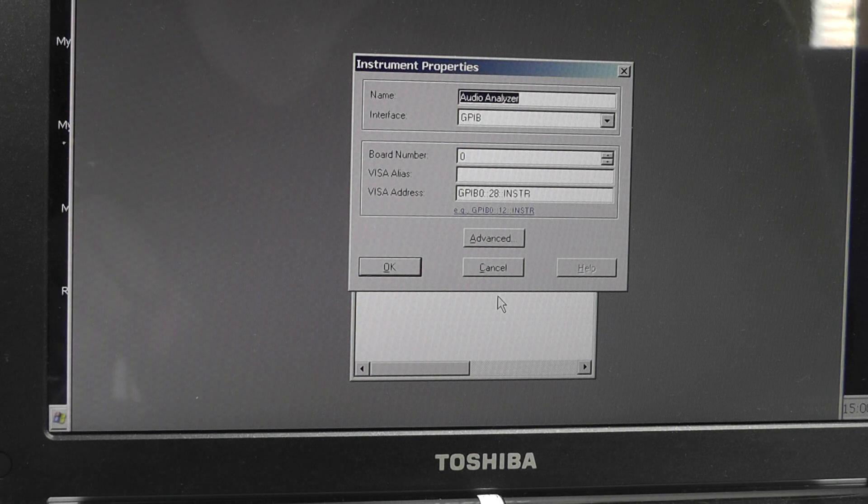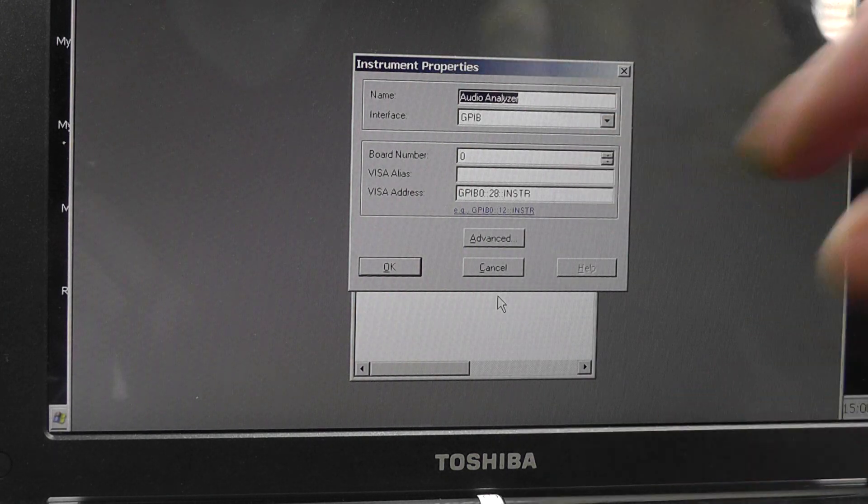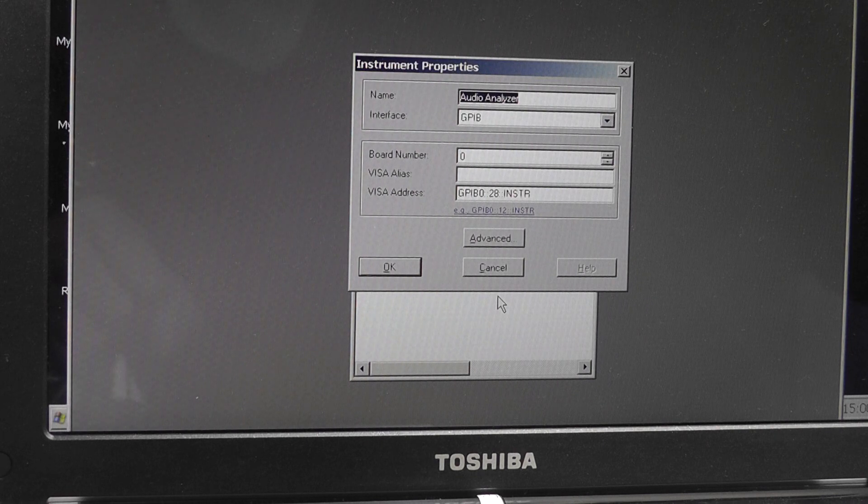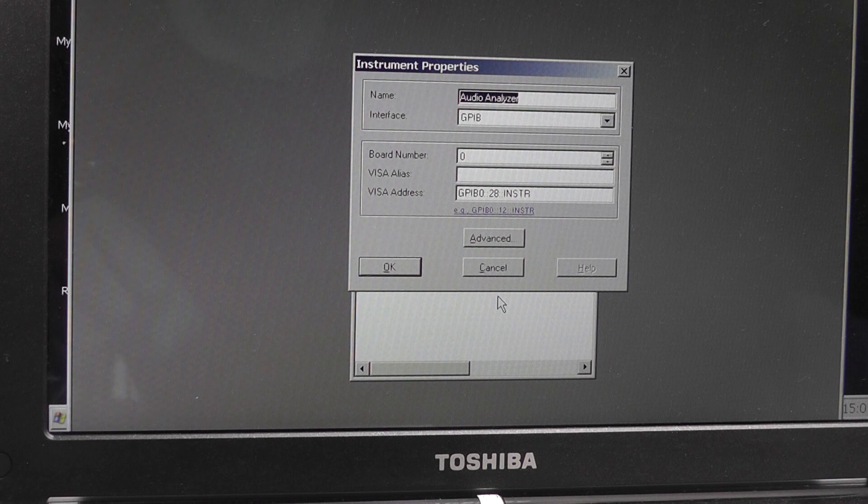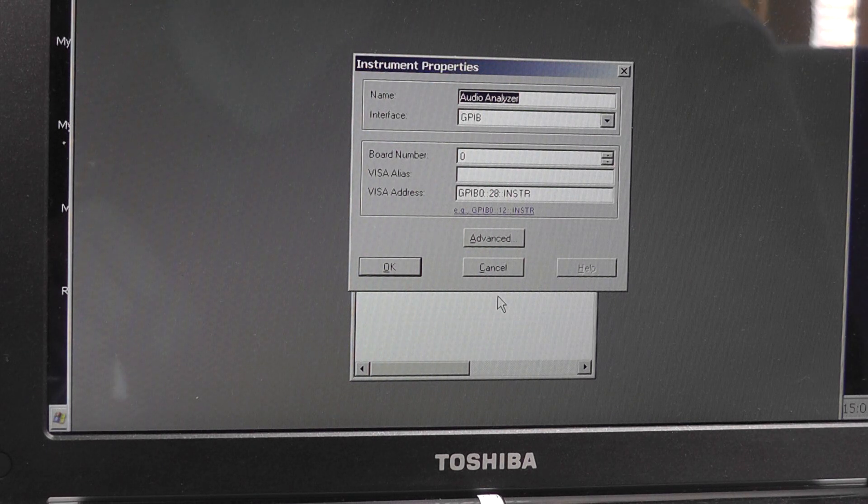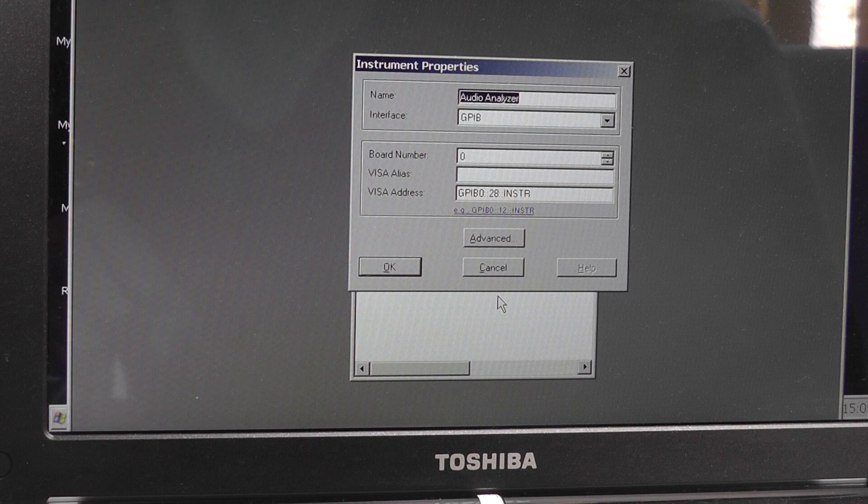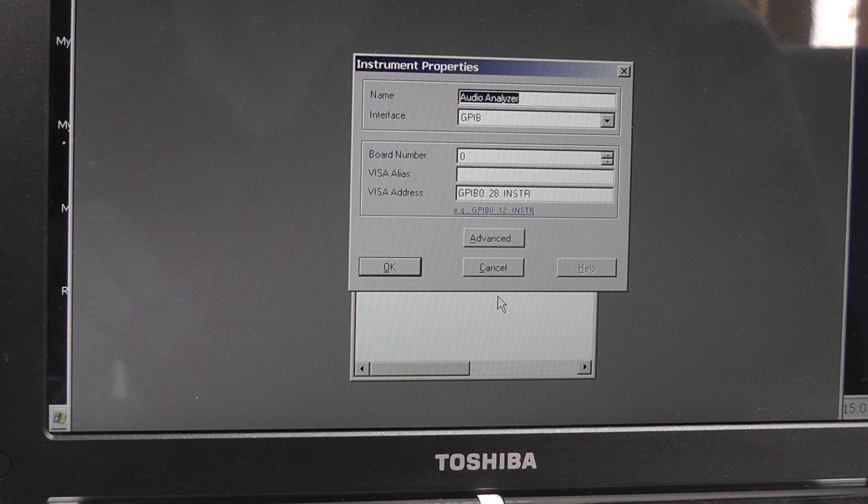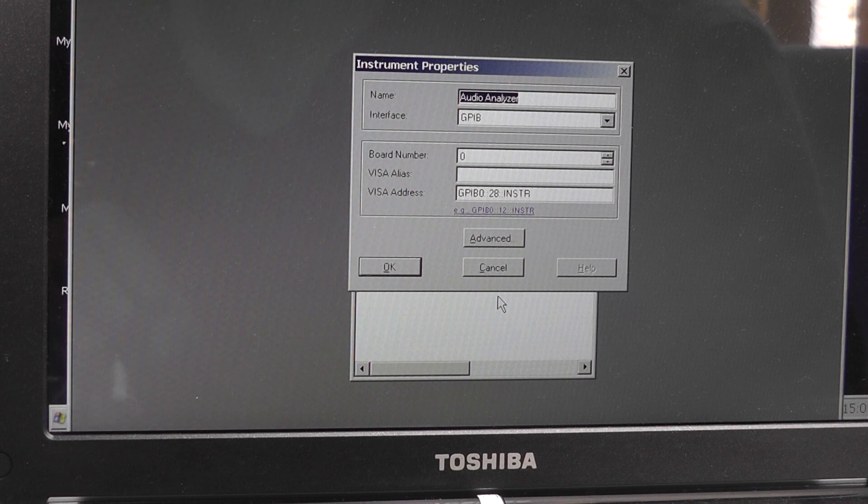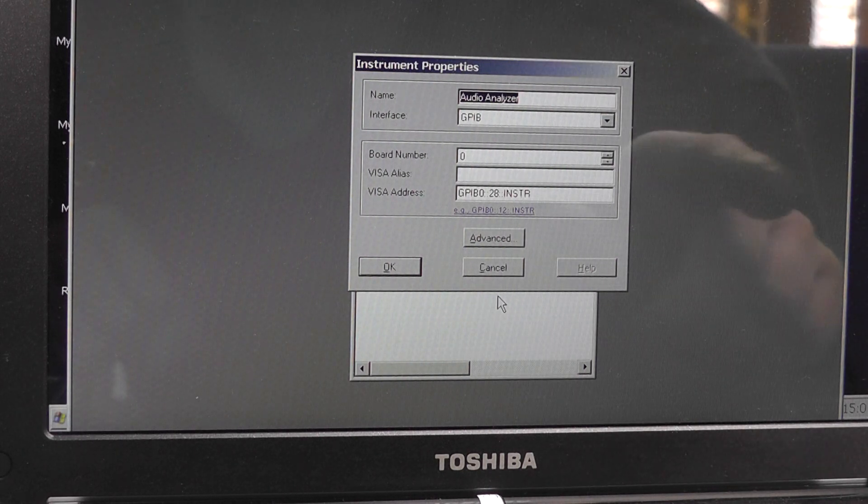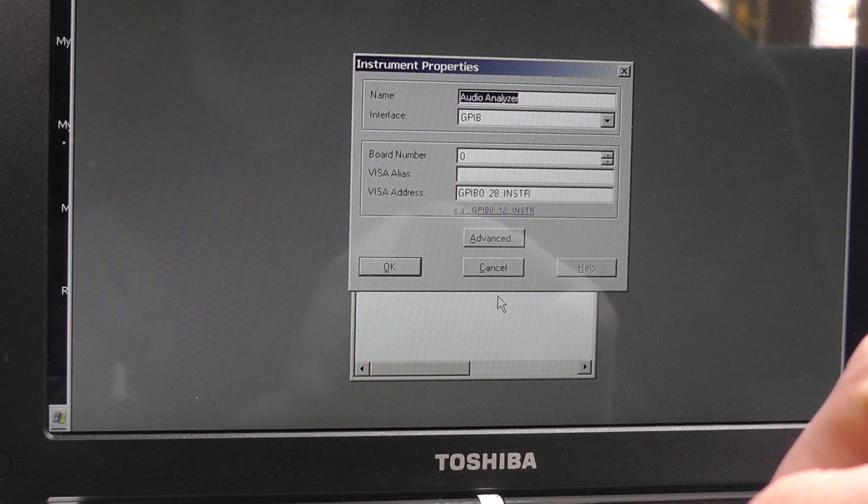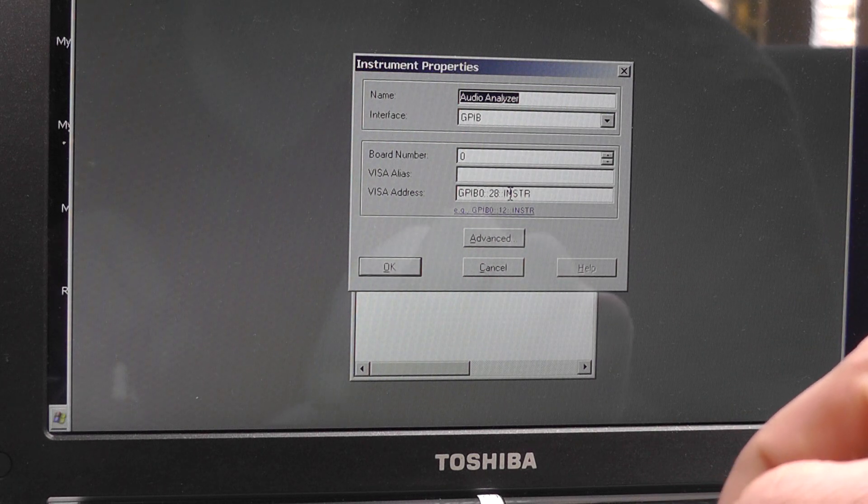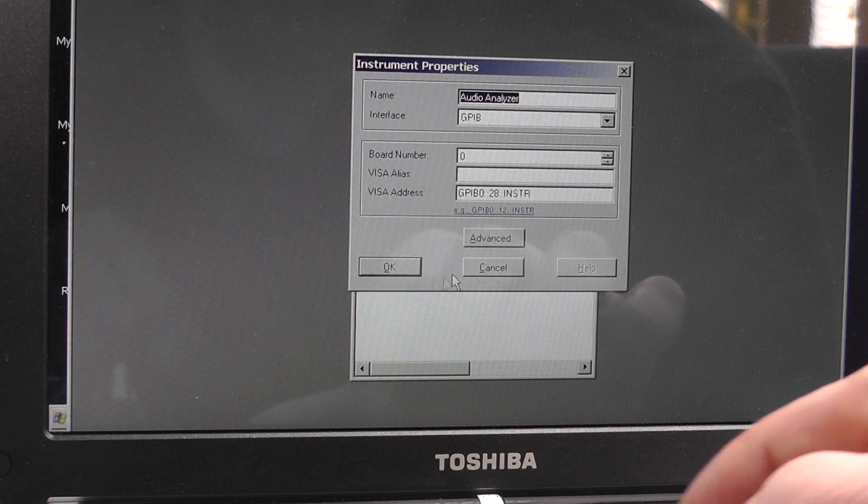Okay, interface should be GPIB. Your board number should be probably zero because that'll be the first GPIB unless you've obviously got other GPIB devices on your system—that's the first device, which is zero. VISA alias—I tried running that with the audio analyzer and that caused confusion with the software when it actually finally got it working. Leave those blank. The VISA address should be, as I mentioned earlier, the GPIB zero dongle address 28, and it just says instrument. That's fine.